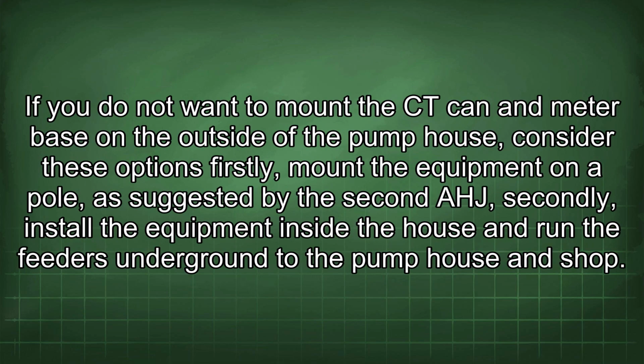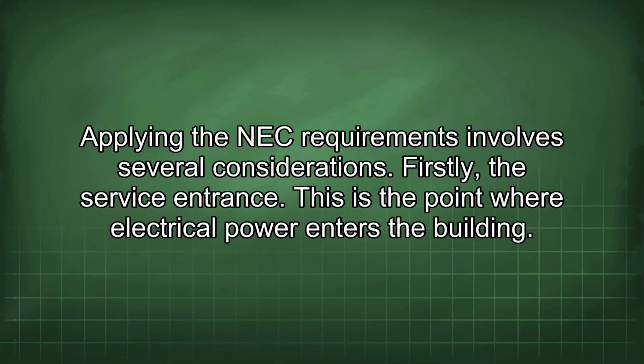If you do not want to mount the CT can and meter base on the outside of the pump house, consider these options. Firstly, mount the equipment on a pole, as suggested by the second AHJ. Secondly, install the equipment inside the house and run the feeders underground to the pump house and shop. Applying the NEC requirements involves several considerations.